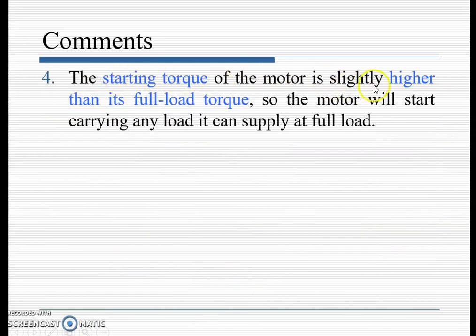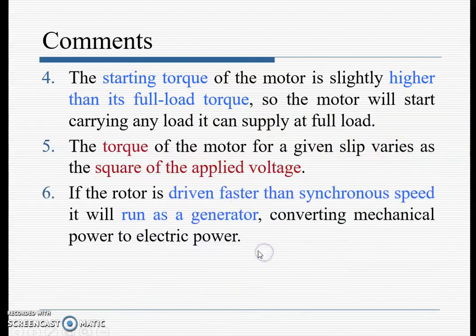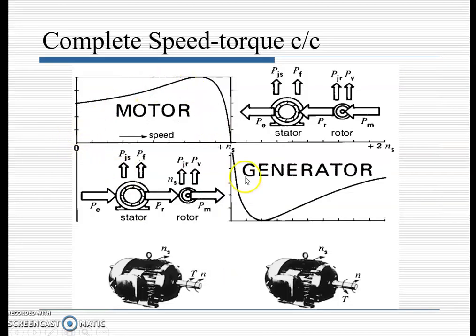The starting torque of the motor is slightly higher than its full-load torque, so the motor will start carrying any load it can supply at full load. The torque for a given slip varies as the square of the applied voltage. If the rotor is driven faster than the synchronous speed, it runs as a generator converting mechanical power to electrical power. Between 0 and n_s the machine acts as a motor; from n_s to 2n_s it works as a generator.